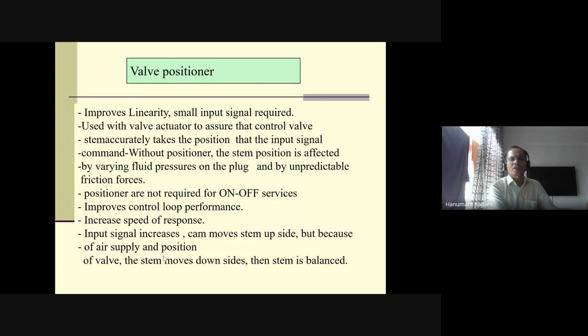So you see the valve positioner improves the linearity, and a small input signal is required. This is very important. With a small signal, 3 to 15 psi or 4 to 20 milliampere coming, you are controlling high pressure valves, and they are linear. Valve position is not like on-off; they are linear. It is used with the valve actuator to assure the control valve stem accurately takes the position that the input signal requires. So with the linkage, it takes the required control position.